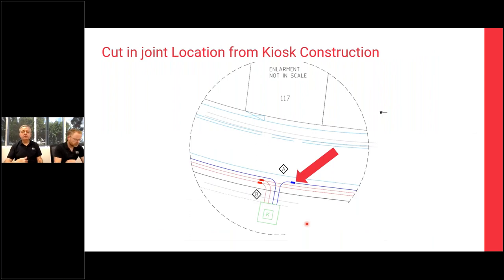You then look at the cable records and see what we've got. And we had here a cut-in joint, which was 20 meters away from that substation B. So this is the source of the discharge itself. So that's what we can do.